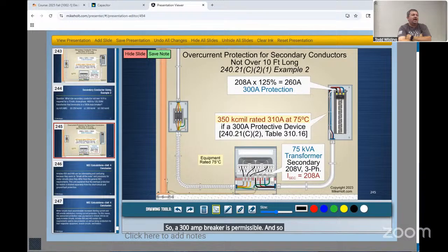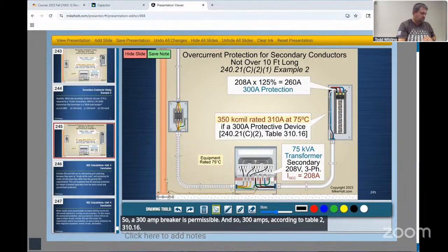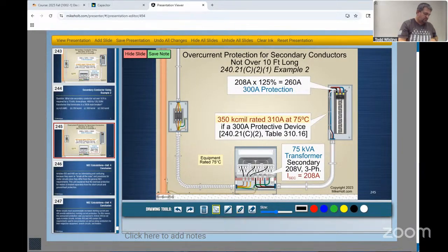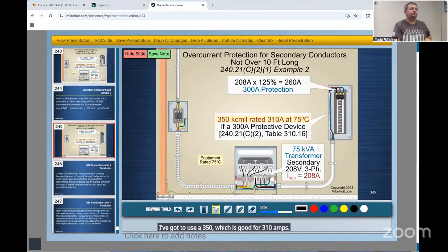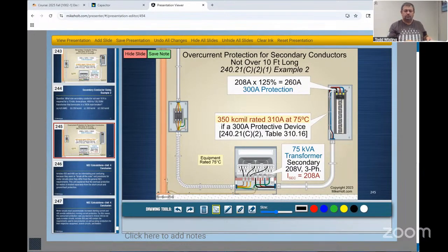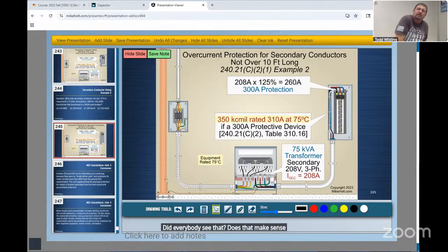And so 300 amps, according to table 310.16, a 300 is good for 285, which does not work. I got to use a 350, which is good for 310 amps. Does everybody see that? Does that make sense to everyone? Again, this is something you will see out in the field.